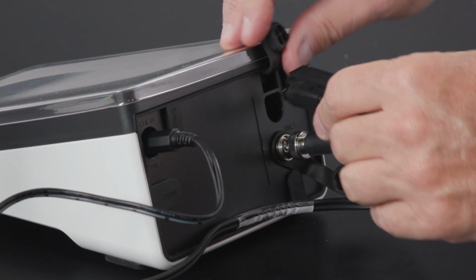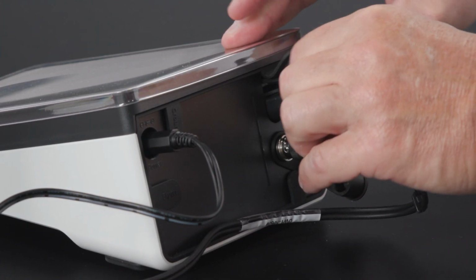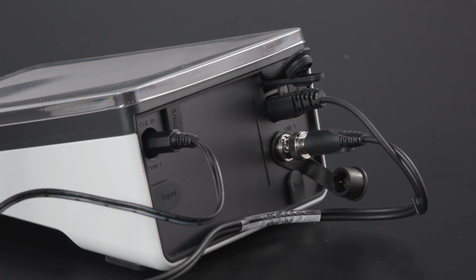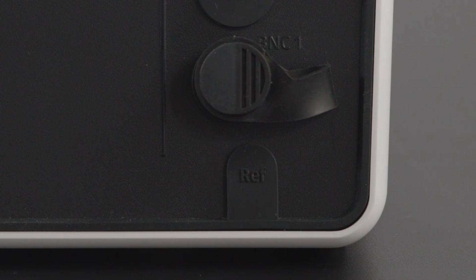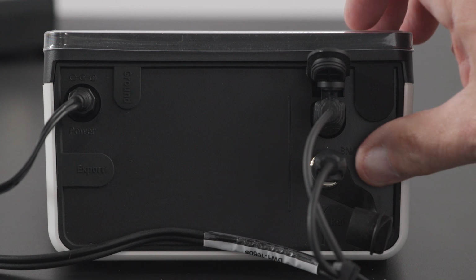To connect an ATC temperature probe, use the 8-pin mini DIN plug. The reference half-cell electrode input accepts electrodes with pin tip plugs. This is only needed when using a reference half-cell electrode paired with a sensing half-cell electrode. The Orion stirrer probe connects with a 3.5mm phono jack.